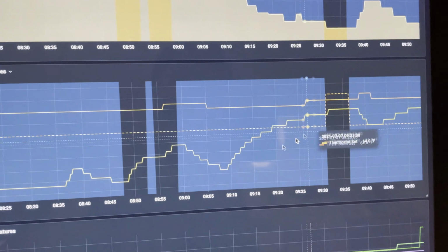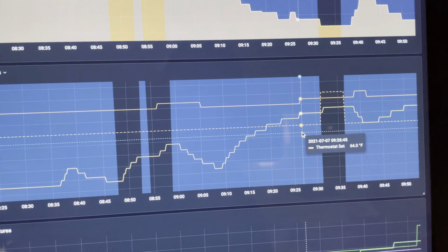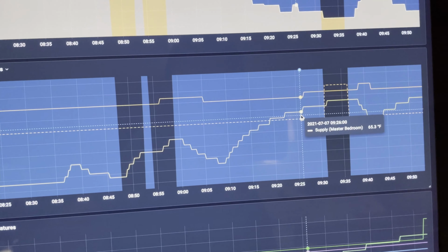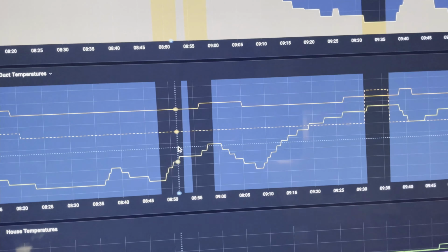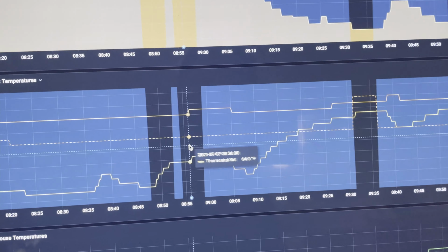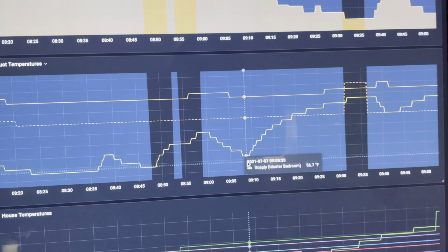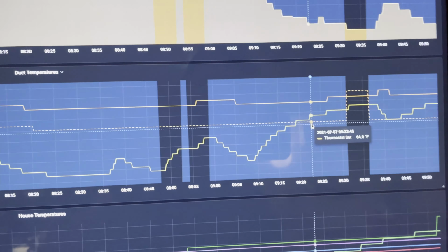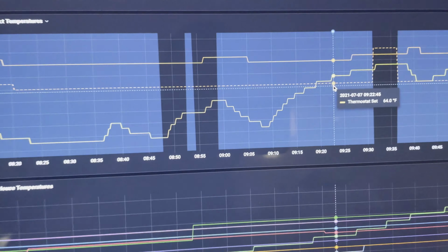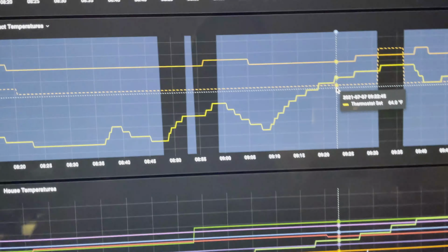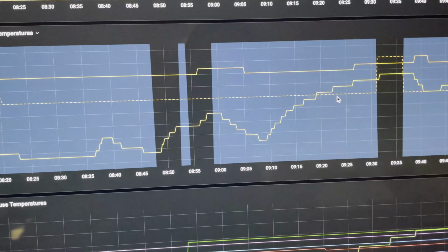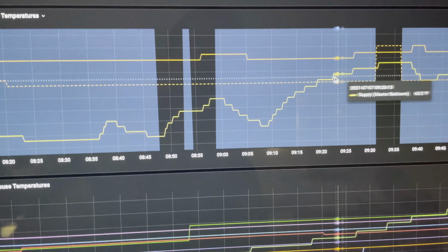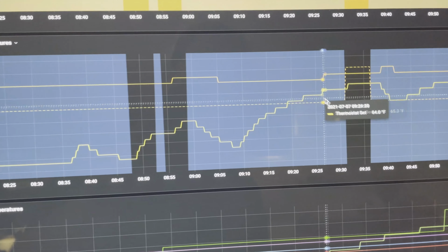This is what it looks like when the compressor's not running. The Nest is calling for cooling, it's not getting cold. That's different than this, where the background goes black because the Nest is not calling for cooling. When this happens, the thermostat is not the problem. The outdoor unit is getting 24 volts. It's getting the signal to cool. The contactor is pulled in, okay? The fan is running. The compressor is not. Thermal overload on the compressor. That's what this looks like.